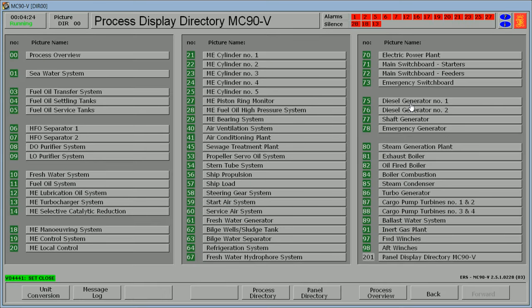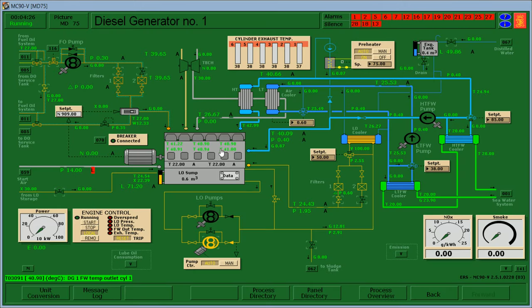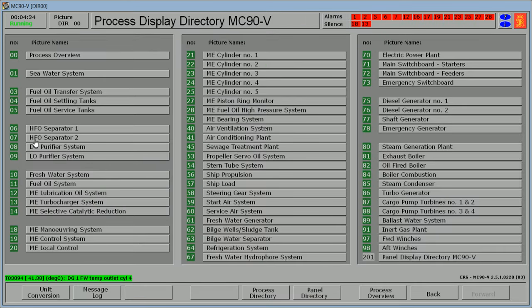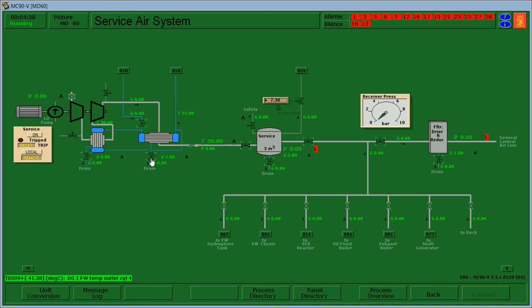So while waiting for your diesel generator to warm up, at least for 50, we must ready the other systems. The service air system, we must drain the water content. So to avoid damage to the parts and components, open the supply air valve, inlet, shutoff valve, set to local, close the drain.